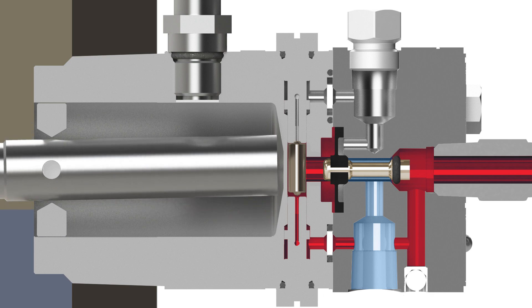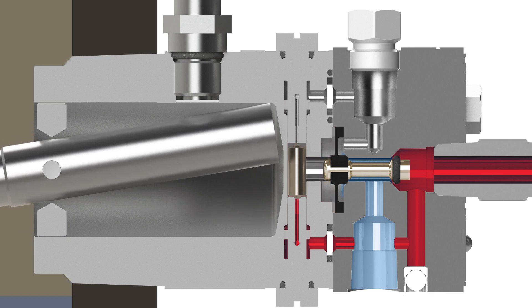As the liquid level and float move down, the lever pivots upward repelling the shuttle back down. This blocks the pressure to the diaphragm which allows the stem to close with the o-ring sealing on the beveled surface.